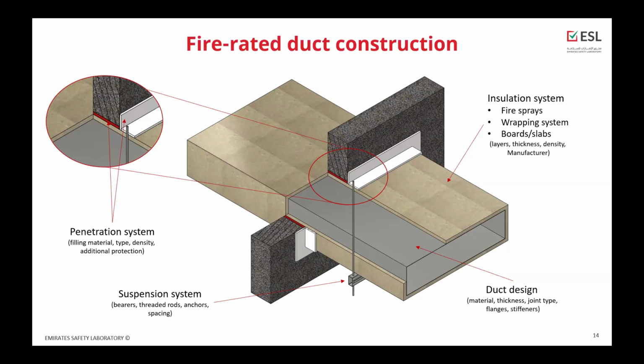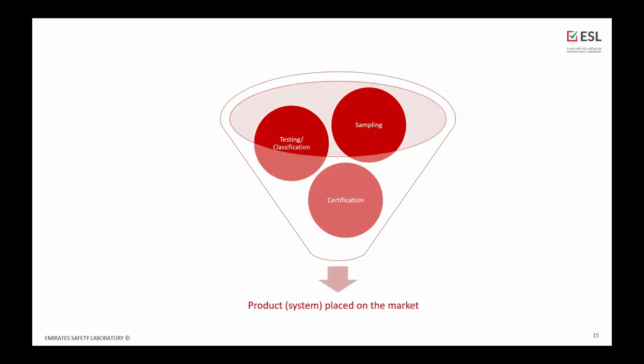The duct documentation also describes how it has to be sealed when it comes through the fire division. So you, as a manufacturer of the duct, need to define how this penetration will be done, and the instruction of penetration and the way of installation must be written either in the instructions or other documents and presented to your clients. So we have three steps of product placement into the market, which are sampling, testing, and certification. Hassan will cover sampling and certification, and I will take you through the testing process.